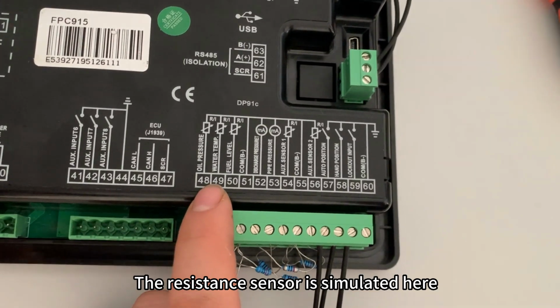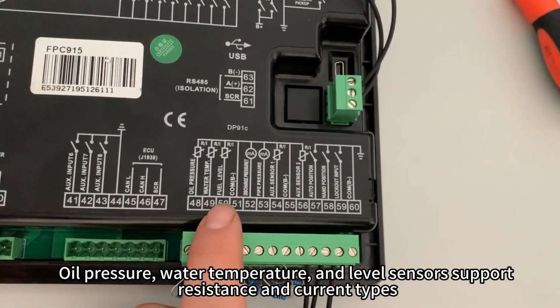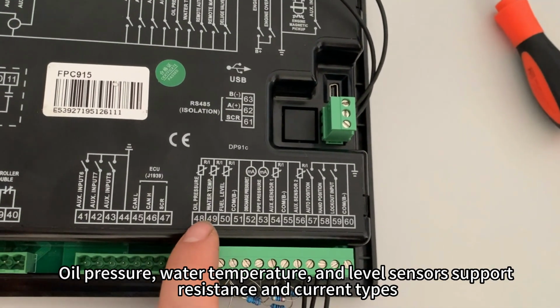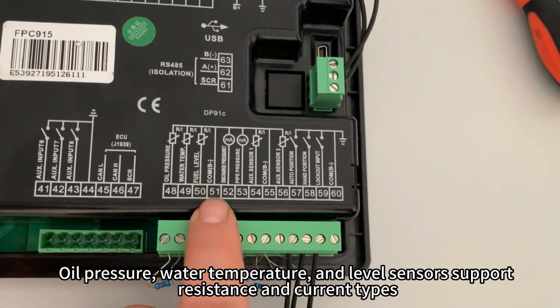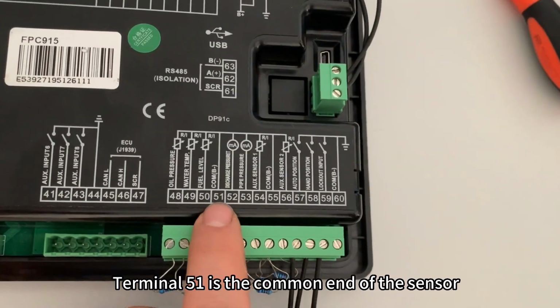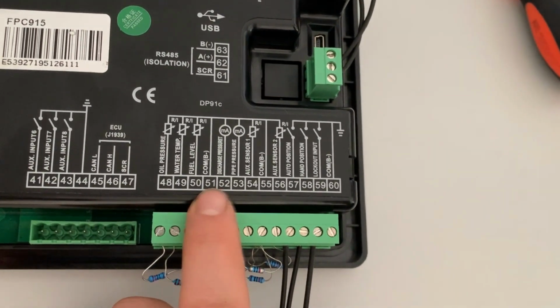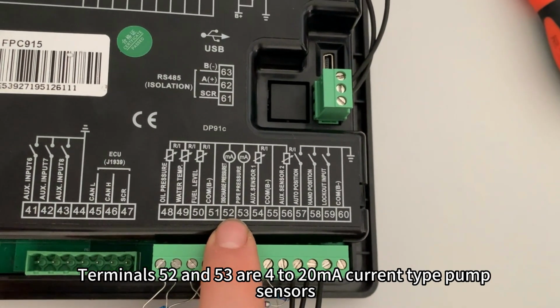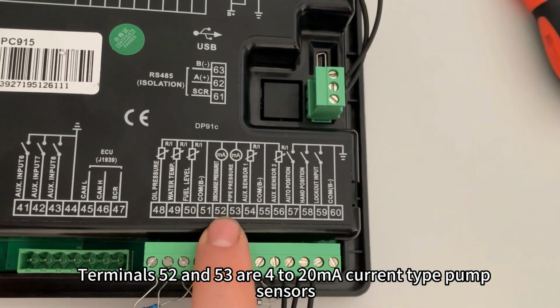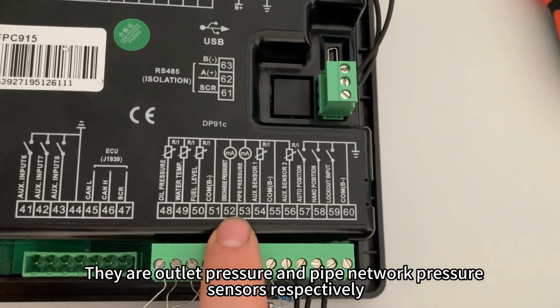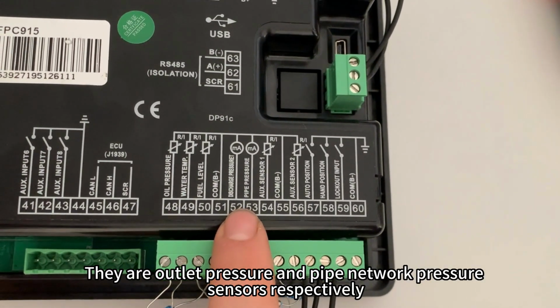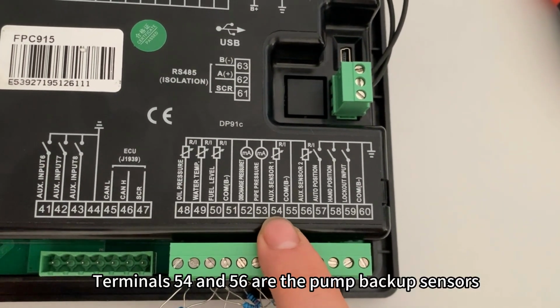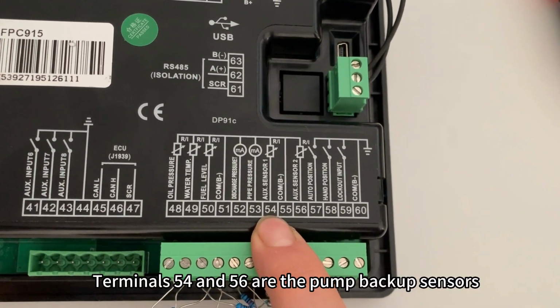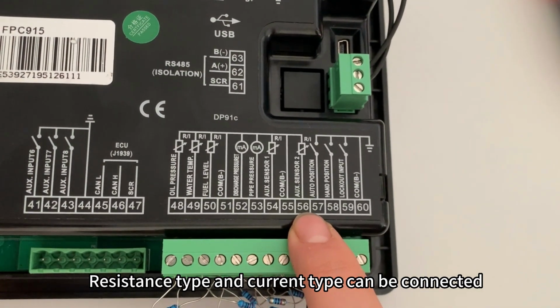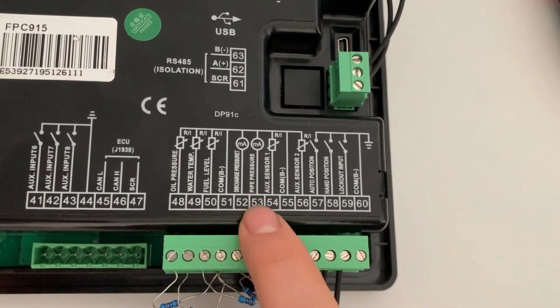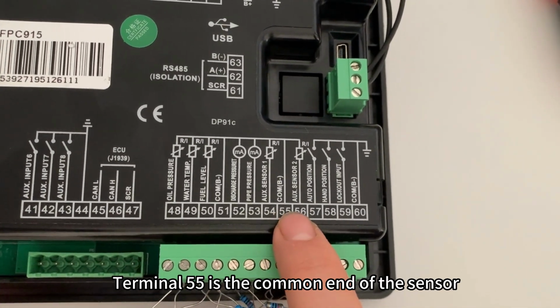The resistance sensor is connected here. Oil pressure, water temperature, and level sensors support resistance and current types. Terminal 51 is the common end of the sensors. Terminals 52 and 53 are 4 to 20 mA current type pump sensors. They are the outlet pressure and pipe network pressure sensors respectively. Terminals 54 and 56 are the pump backup sensors. Resistance type and current type can be connected. Terminal 55 is the common end of the sensors.